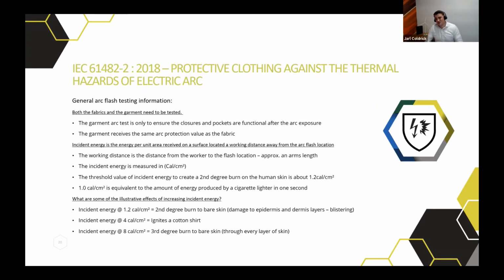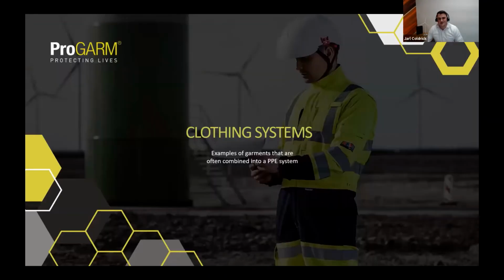Some illustrative effects: an incident energy level of 1.2 cal can cause a second-degree burn to skin. An incident energy level of 4 cal can actually ignite a cotton shirt. And an incident energy level of 8 cal can cause a third-degree burn. So it's essential to know what you're up against and calculate the incident energy level required to protect against.